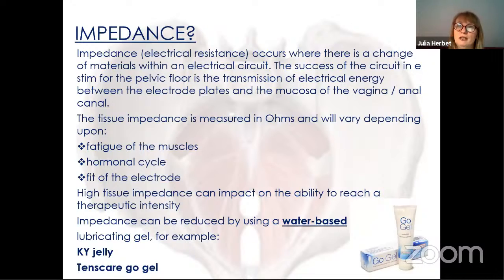So one of the problems that we come across is that we're not actually plugging the patient into the electrode. If I want to charge my laptop, I will plug the plug into the main socket, and there'll be metal pins on the plug and metal in the socket, and they make a really good fit and a really good contact. We don't have that in the human body. So we're actually placing the electrodes next to the vaginal skin, which is a mucous membrane, which hopefully is quite moist. But actually adding a lubricant will make that a better contact.